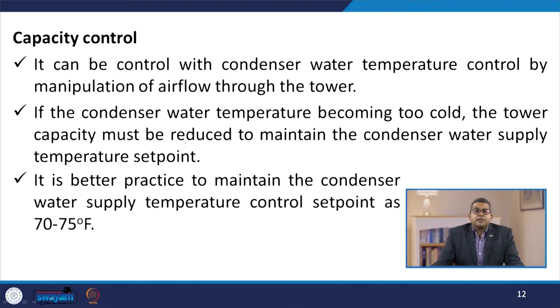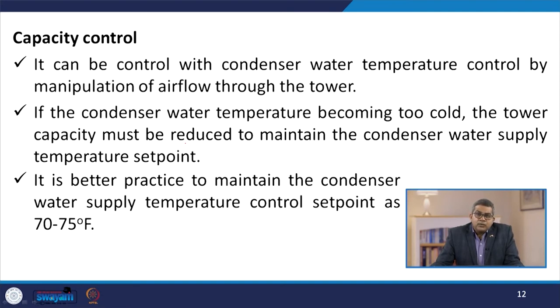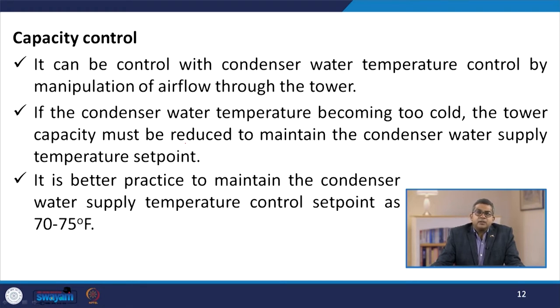Let us talk about the capacity control. The capacity can be controlled with condenser water temperature controlled by manipulation of airflow through the tower. If the condenser water temperature becomes too cold, the tower capacity must be reduced to maintain the condenser water supply temperature set point. It is a better practice to maintain the condenser water supply temperature control set point at 70 to 75 degrees Fahrenheit.